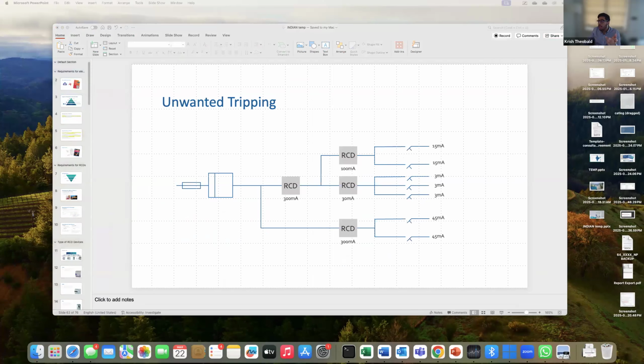It's very simple. Important to realize, if you have the wrong type of RCD selected, let's say you have a type A selected where a type B was required, or a type AC selected, what happens, like Gerard mentioned, is that the RCD gets saturated and then it will not trip at all. So forget nuisance tripping. You will think everything is perfectly fine, but in reality, your RCD has got saturated and it cannot trip. That is why the selection of the right type of RCD is extremely important.